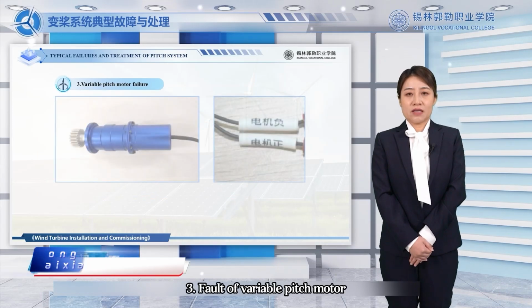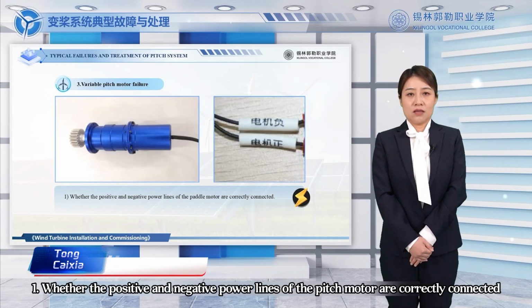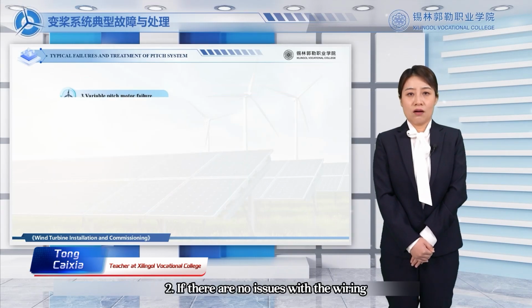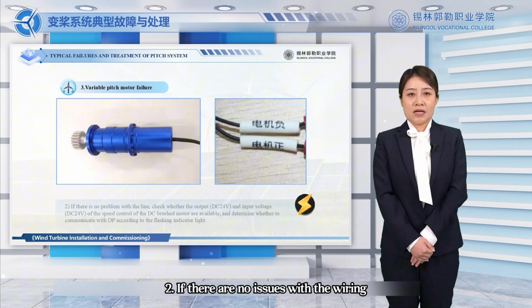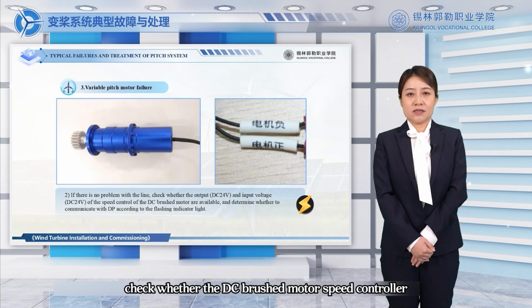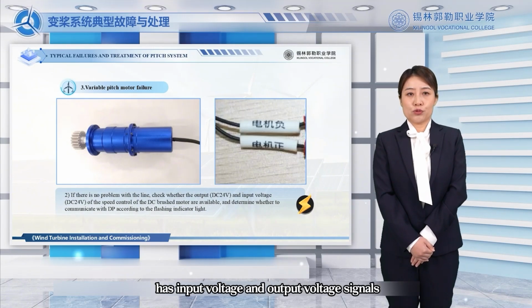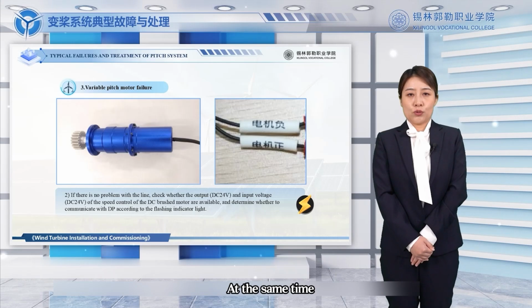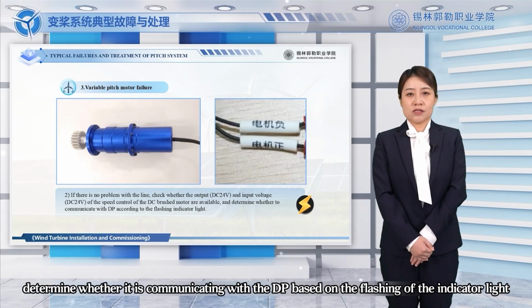3. Fault of the pitch motor. 1. Check whether the positive and negative power lines of the pitch motor are correctly connected. 2. If there are no issues with the wiring, check whether the DC brushed motor speed controller has input voltage and output voltage signals. At the same time, determine whether it is communicating with the DP based on the flashing of the indicator light.